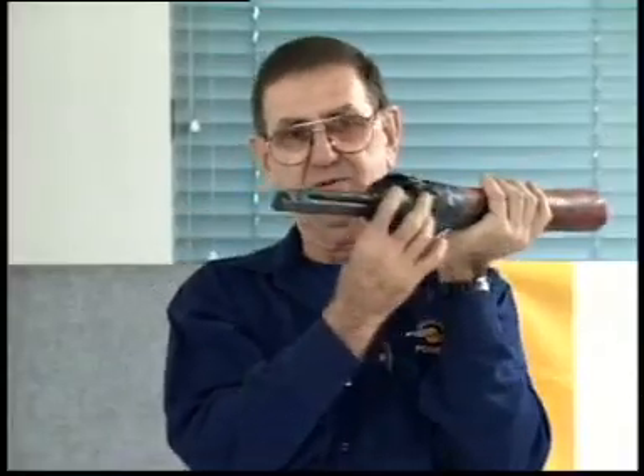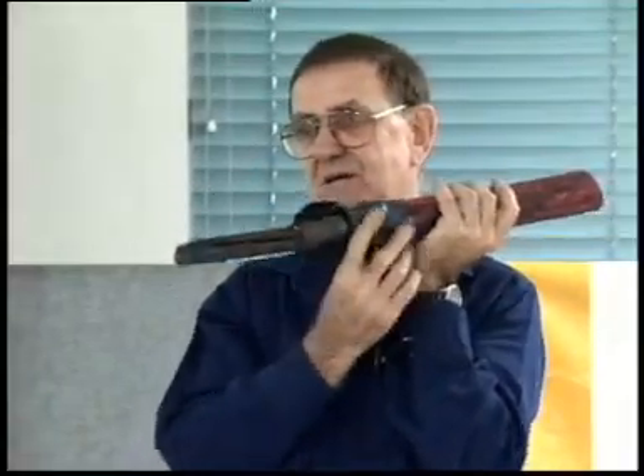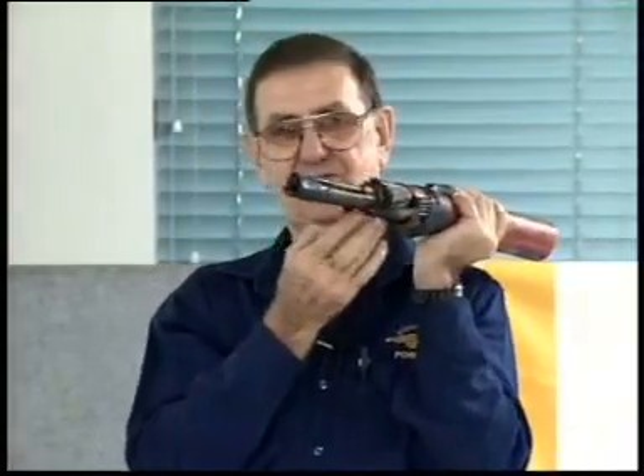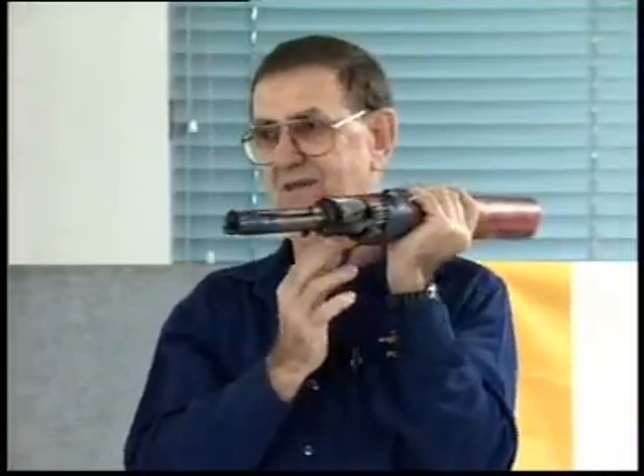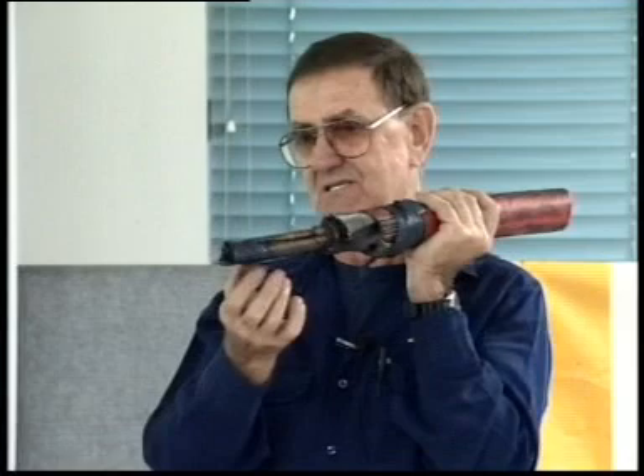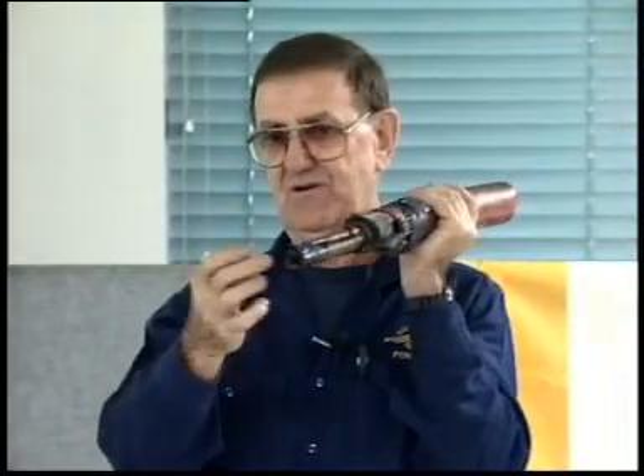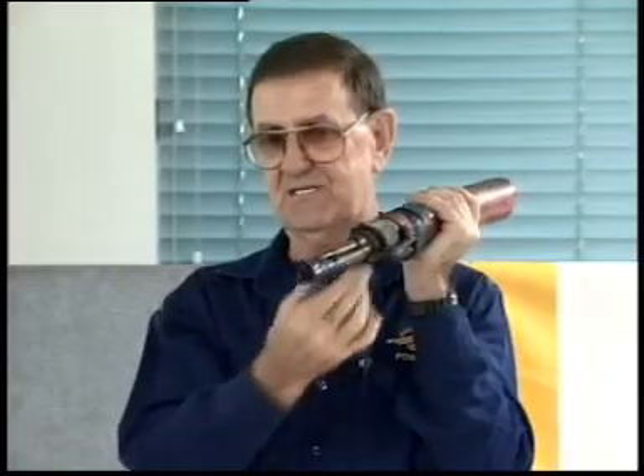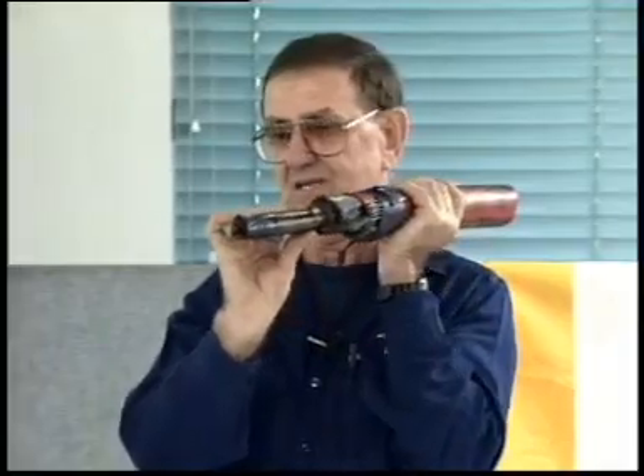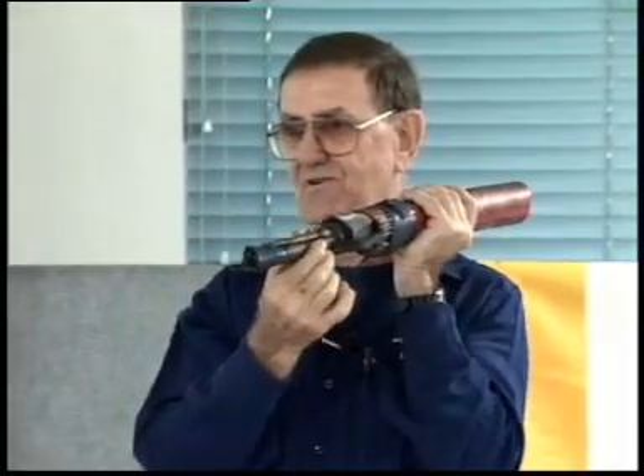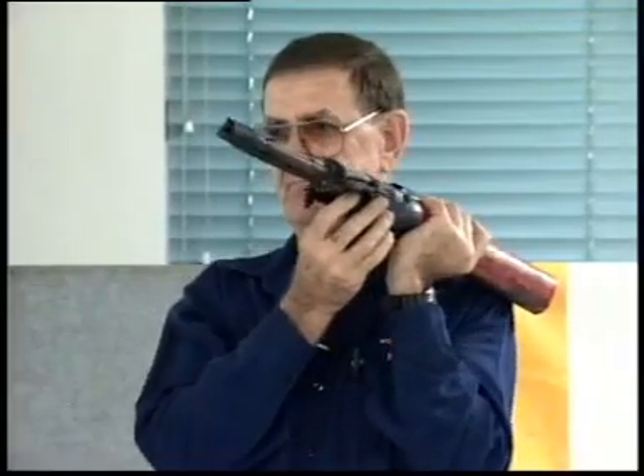Now if you crack this lead open for any reason, if the lead cracks open, this oil will gradually find its way out. It doesn't run out, it's not that thin, but it can work its way out. We found it on the outside of the cable in many instances. So once the oil starts to run out of these papers, they start to dry out. Once they start to dry out, the resistance to the voltage inside reduces, so that means you can get a flash. Now because you've got 3 phases sitting closely together, the worst thing that we can have occur is a phase-to-phase fault, which is normally what happens with these things. So it's important we don't crack this lead open.